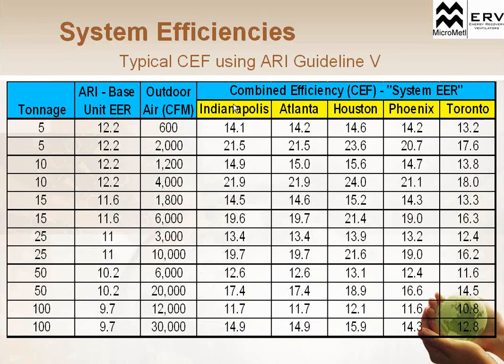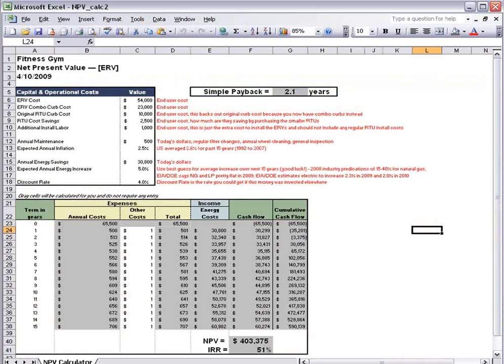If we take a quick look, just on average, we've got a couple different areas. We look at Indianapolis, on an average 10-ton rooftop system with 4,000 CFM of outside air, we get an average combined efficiency of 21.9 EER. Now that's significantly higher than your standard rooftop unit, which is maybe anywhere from 10 to 13 EER. So you're getting much higher combined efficiency values, which are outlined in this guideline on how to calculate. And that's where you're getting the energy savings, and that's what applies to that LEED type of credential towards your building. There's also individual savings calculators where we can provide the software to you, but it's very basic.